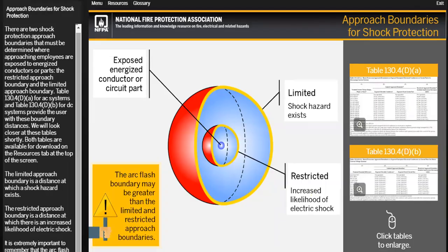It is dependent upon voltage. The higher the voltage, the greater the limited approach boundary, and you have to keep unqualified people away from it. The restricted approach boundary is the boundary in which a qualified person with personal protective equipment will be working on the system while the system is energized, taking all the safety measures and practicing electrical safe work practices, and only a qualified person can do this.